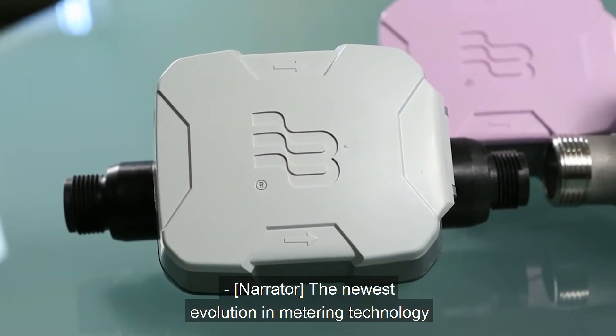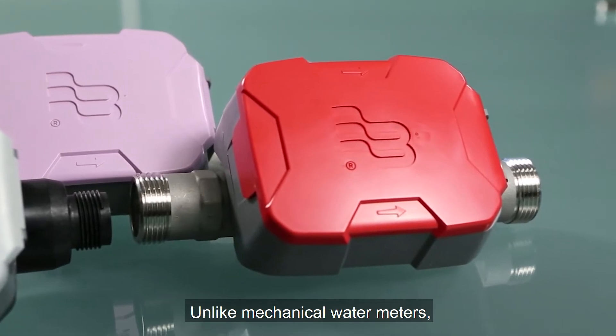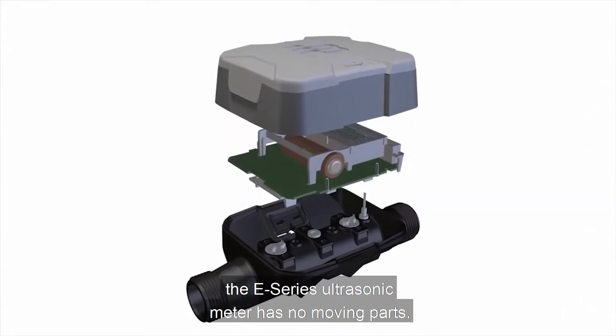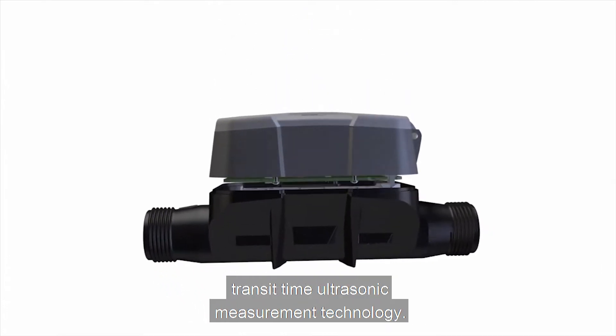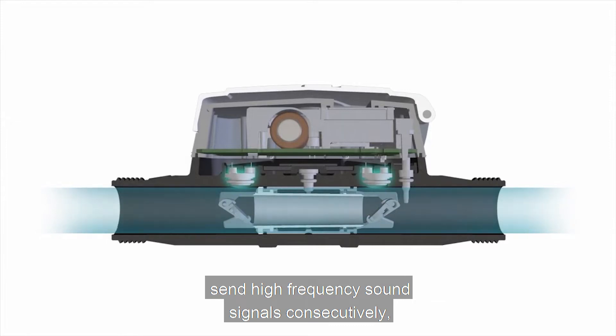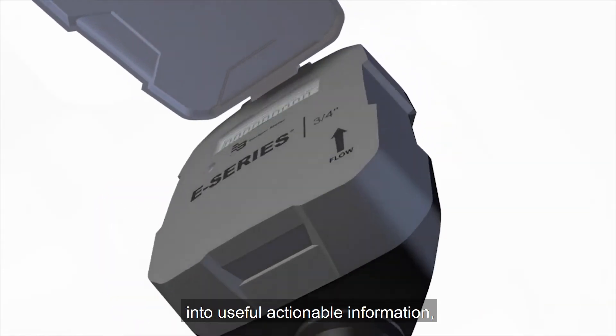The newest evolution in metering technology is the Badger Meter E-Series Ultrasonic Meter for potable, reclaim, and residential fire service applications. Unlike mechanical water meters, which rely on moving parts to measure water flow, the E-Series Ultrasonic Meter has no moving parts. It uses solid state electronics and transit-time ultrasonic measurement technology. Inside each E-Series Meter, two electronic transducers send high-frequency sound signals consecutively in forward and reverse directions. An onboard microprocessor turns the water data into useful, actionable information.